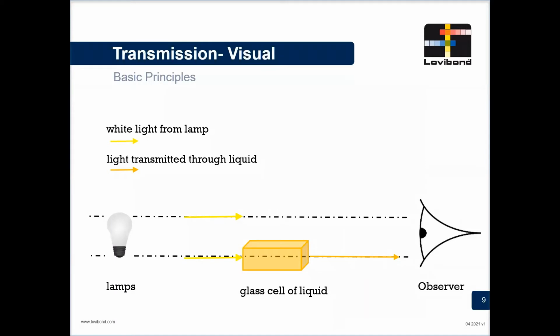So this instrument has a light source, and we're shining that light source down two optical paths. So one, we're going through our edible oil in our glass cell, and the other, we're shining it through a path where we can put different coloured glasses in so that visually you can look down the eyepiece and see what's happening. So here's our light coming into the eye. At the moment the colour isn't matched.